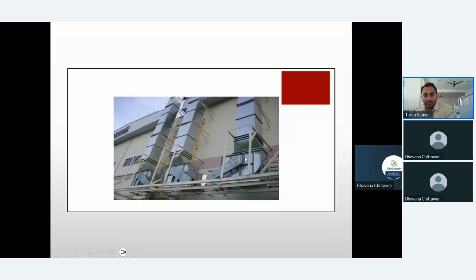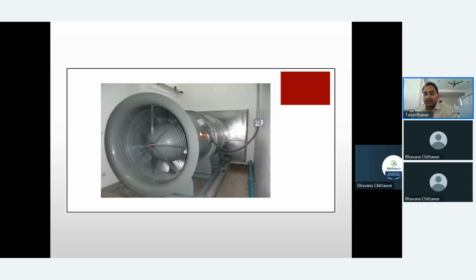Here is one more example. Whenever you are putting a straight duct over the fan, try to give separate support for the duct. Whenever the fan manufacturer selects the isolator for the fan, they calculate the weight only for the fan, not for the duct. In that case, your complete duct load will come on the fan, proper isolation will not happen, and your bearing will fail immediately.